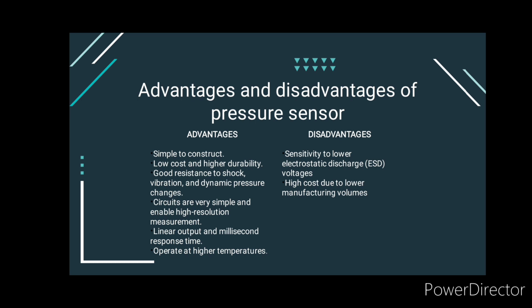So, here's an example of advantages and disadvantages of a sensor. Advantages: so simple to construct, low cost and high durability, good resistance to shock, vibration, and dynamic pressure changes. Circuits are very simple and enable high resolution measurement, linear output, and millisecond response time. Operate at higher temperatures.